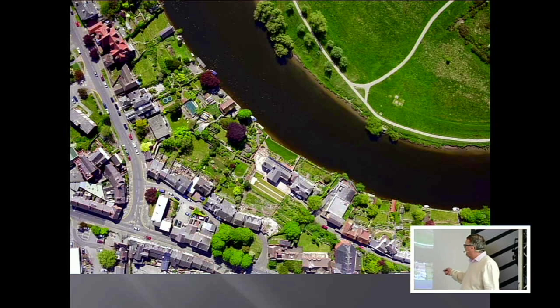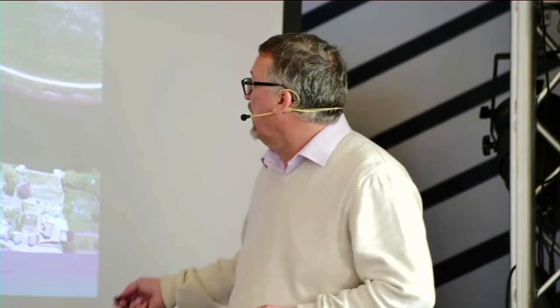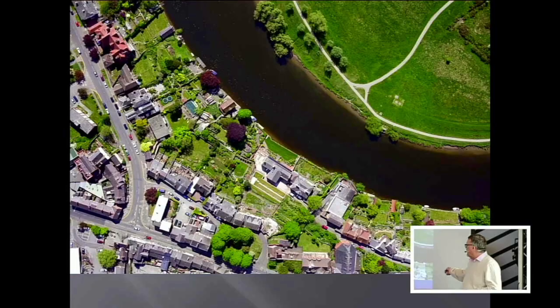The reason, obviously, I mentioned it's underground, inside it are two giant sieves. So they're sieving out all leaves and twigs and material litter and things that can be in the river, simply because you don't want to start pumping that through pumps, because pumps will wear out quicker. They can snag, they can jam, and it's a very expensive process to replace a pump. So all the fines and that taken out, and you can see the leaves and that being washed back into the river at that point, because the screens are washed by backflow of the wash water from the river itself.